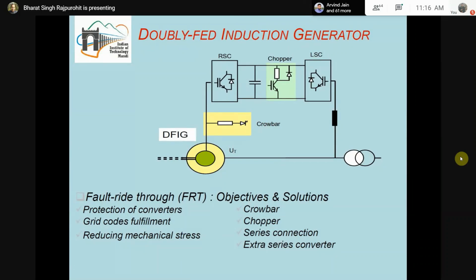Crowbar is known as a non-linear resistance controlled by some power electronic semiconductor switches, which are connected here. So how is this working? If the chopper is not able to control or dissipate the extra amount of energy in the rotor circuit, the crowbar will come into the picture.